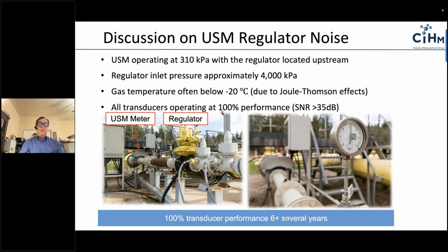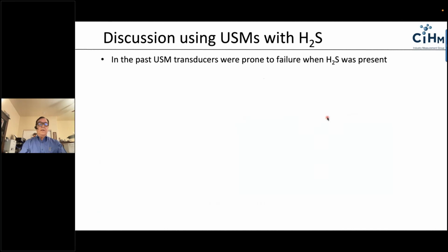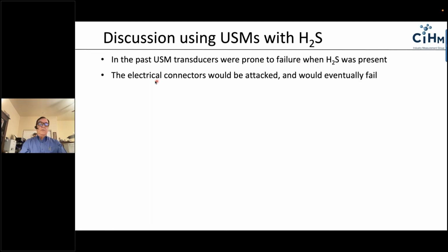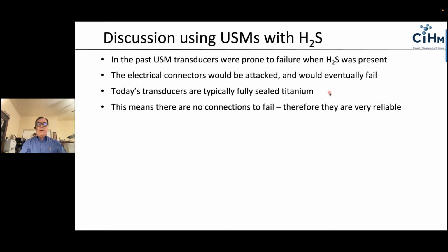This meter's been in operation for 6 years, 100% transducer performance, no failures. So I use this as a method to show Kiura that this meter can handle the kind of differential that they're looking at. The last topic of discussion, before we turn it over to some questions, is that past ultrasonic transducers have been prone to failure with high H2S. The reason is that the electrical connectors get attacked by the H2S and eventually cause the transducer to fail. But today's titanium transducers are fully sealed, so there are no electrical connectors being subjected to the gas and the hydrocarbon, the H2S.